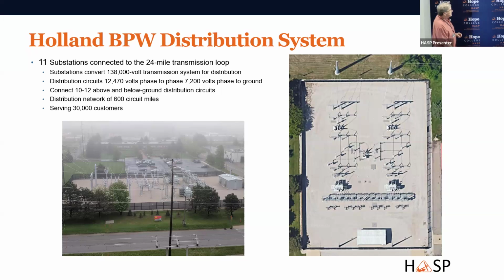If you look at the Google picture on the right, at the very top you'll see a pole - that's where the 138,000 volt loop comes in on the left-hand side. It goes through circuit breakers and switches, and eventually down to a large silver-looking thing, which is a transformer. Across the bottom are a row of distribution switches that go out to our homes and factories. On the other side you'll see another transformer, and then where the loop comes back out - so it comes in and comes out.